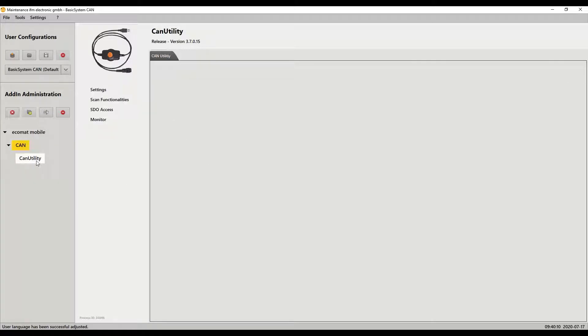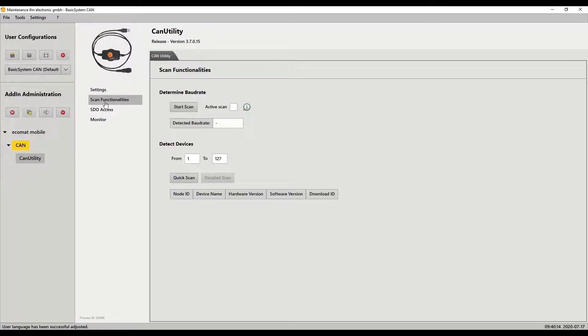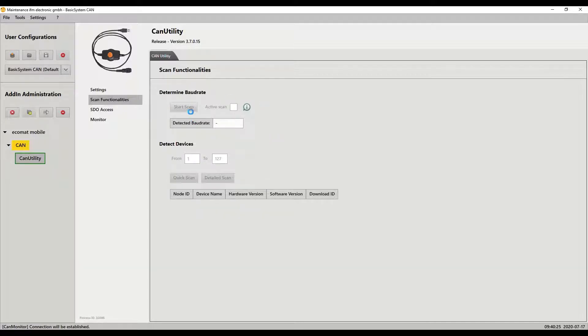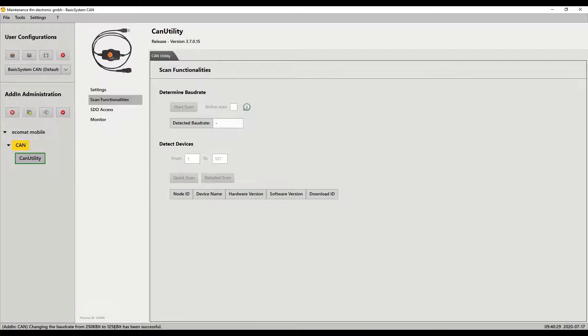So we click on the CAN utility and then we're going to go to the scan functionalities. First we're going to scan for the baud rate. You don't need to do this - they default to 125 - but for this video I just want to show you how this works. So we scan and then in the bottom of the screen you'll see it going through, changing the baud rates, and it finds the device at 125.